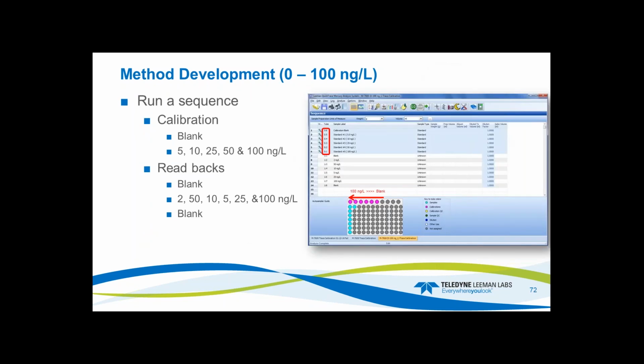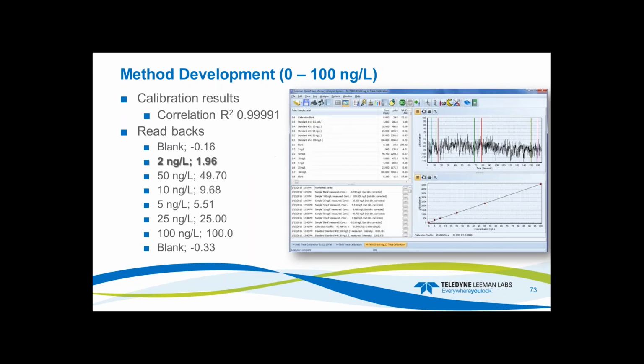Run the sequence, and every time I do the readbacks, I like to mix it up to look for problems within the calibration, which I showed you in the 0 to 1,000. We saw a problem with the intercept. The correlation was very nice, but when you're trying to do a large dynamic range, you have to dot all your I's and cross all your T's. So here I read back 2, 50, 10, 5, 25, 100, and then the blank after the calibration, and look at this: my correlation was four nines and a 1. That's pretty awesome. Blank's flat and straight across.